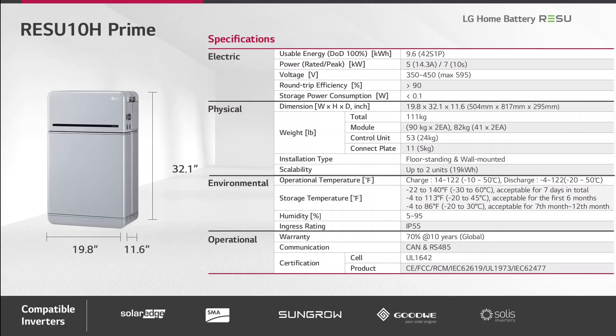Let's have a look at the datasheet of the Resu 10H Prime. This battery is very compact and has a total weight of 111 kg. Due to the weight, you have two installation options: floor standing and wall mounted. You can also expand the system by a further unit resulting in 19 kWh of energy content. It has an IP55 rating, so it can be used inside or outdoors. The BMS offers two communication protocols, CANBUS and RS485. This battery will be compatible with inverters from SolarEdge, SMA, and later also SunGrow, GoodWe, and Solis.